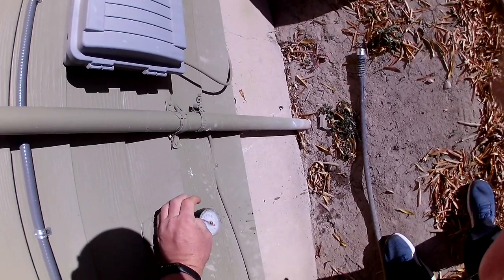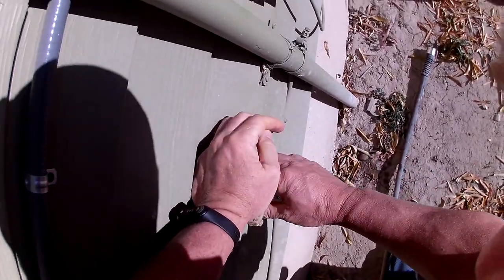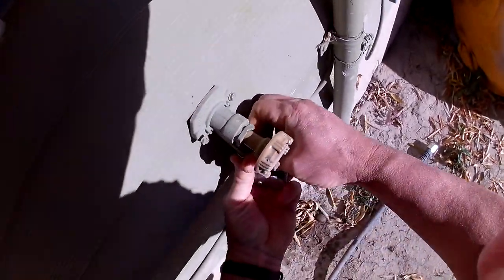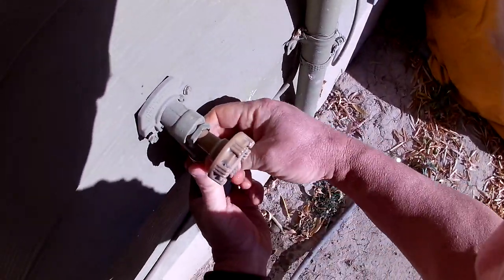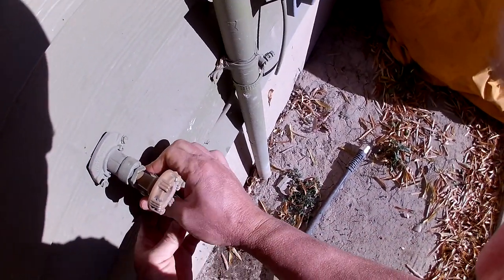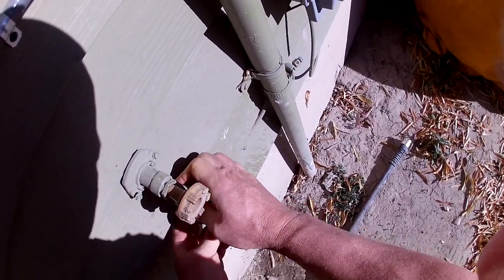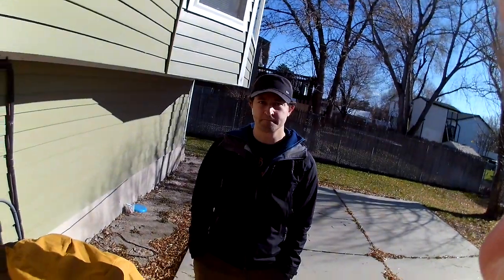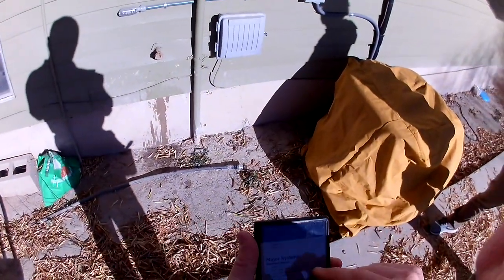Now you've got 120 psi, which is a lot. Should it be like max 110? Yeah, I like to see them between 40 and 90. Okay. And so really this is a measure of the city, but where it should be turned down via the pressure reducer inside the house. Yeah. So it might be a bad pressure reducer valve. Yeah, or none at all, given the age. So I'm going to write in we got 120, and that's high.